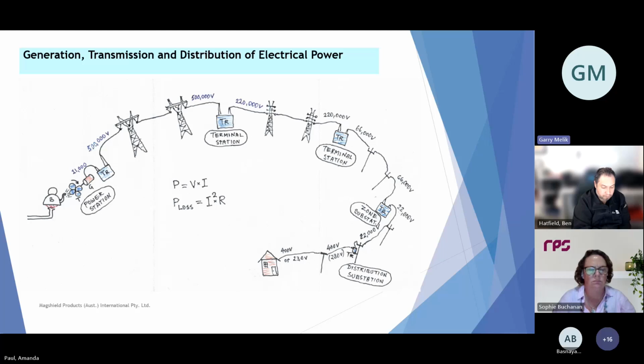You have a transformer which increases that to 500,000 volts. The reason the voltage is going up is that your aim is to transmit as much electric energy as possible. Now, the electric energy equation is in the middle: electric power is the product of voltage and current. If you want to transmit very high power, you have to have high voltage and high current. Now, if you have very high current passing through wires, it causes power losses. In order to minimize power losses, what happens in the power system is we tend to increase voltage as much as practicable in order to reduce current, so that we minimize the losses.